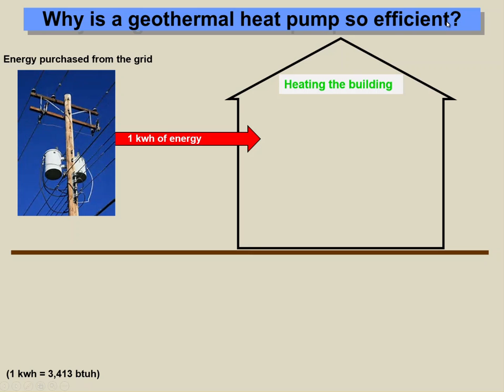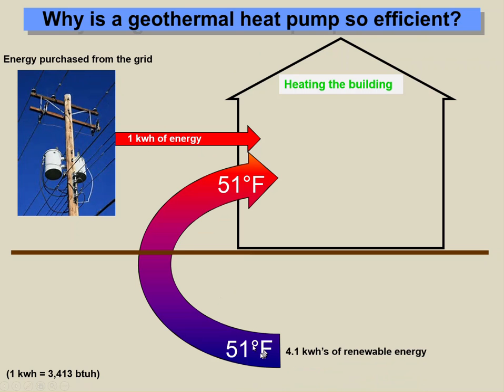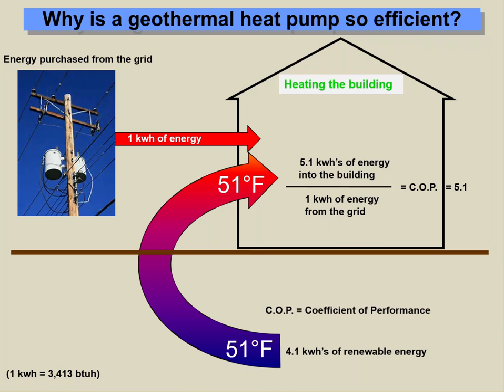In heating the building, by buying 1 kilowatt hour of electric energy to run the heat pumps, they extract out of the 51 degree groundwater 4.1 kilowatt hours of renewable energy. And the electric energy coming in to run the equipment doing work is converted to heat. So there are 5.1 kilowatt hours of energy entering the building, and you paid for 1 kilowatt hour of energy, and that yields a coefficient of performance or efficiency of 5.1.